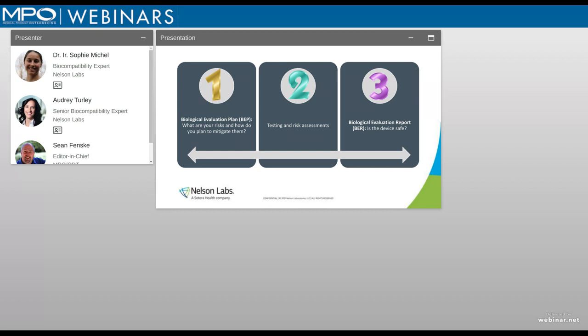And this will be done in a biological evaluation plan, in which you're going to evaluate all the data that you have on your product and how you're going to address the safety of your product, and so actually which strategy you're going to develop. This, of course, needs to be performed before you step into testing, and naturally also before you actually evaluate the safety of your product in a biological evaluation report.